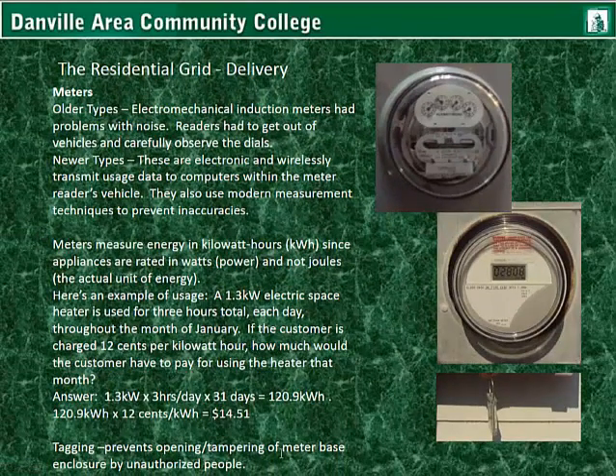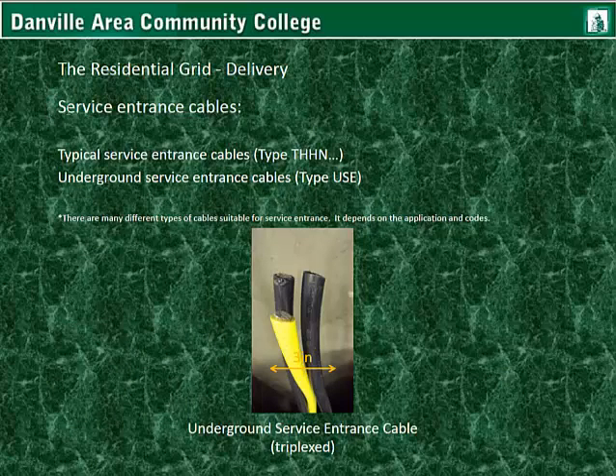Tagging prevents opening and tampering of the meter base enclosure by unauthorized people. It's a special clip with its own code on it. Service entrance cables — the typical service entrance cable ran in conduit would be type THHN, and there are other types. Another type used is the underground service entrance cable type USE, which can be run straight underground without any conduit. There are many different types of cables suitable for service entrance, and it depends on the application and codes.